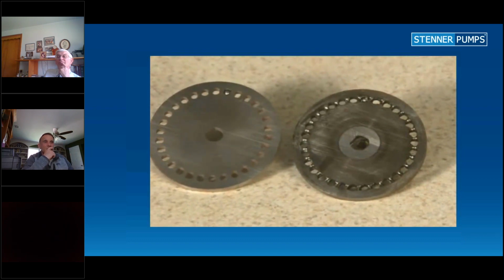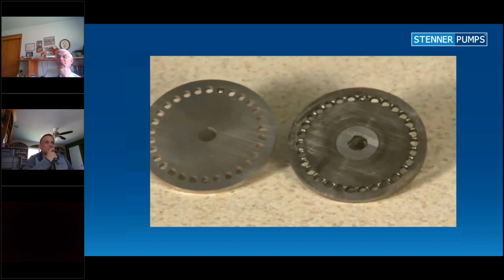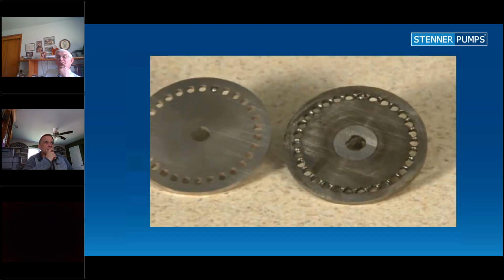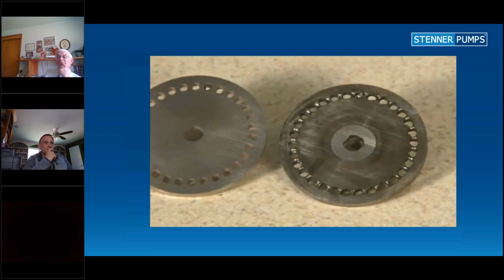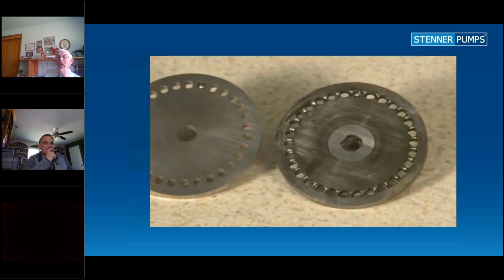A worn cam and/or lifter can cause the index pin to drag across the index plate and elongate its holes. The pin will skip across the holes and cause index malfunction. At the beginning of the maintenance section, we reviewed installation points that best suit the pump. The vertical mount with the pump head pointing in the downward position is important for the feed rate control too. Corrosive chemical intrusion can corrode the index pin and/or the lifter, causing them to seize. The feed rate will malfunction and the parts will need to be replaced.